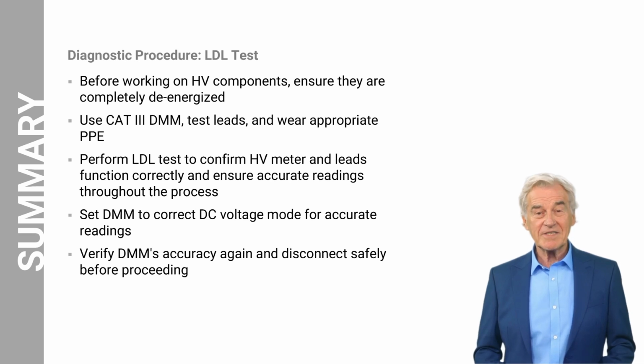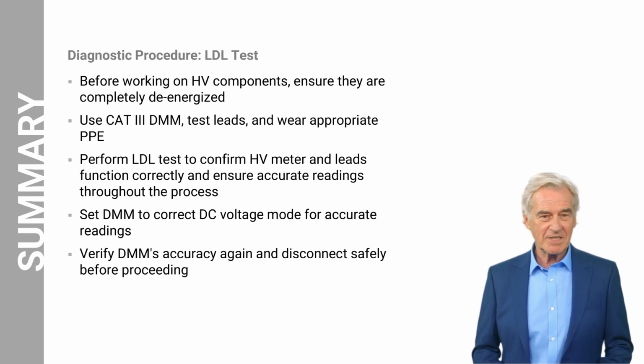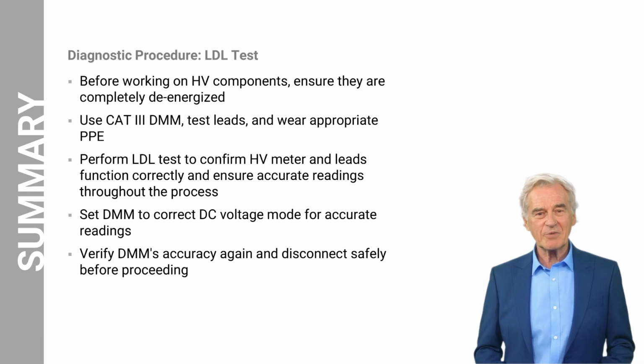Setting your multimeter to the correct DC voltage mode is critical for accurate readings, preventing false assumptions and potential safety hazards. Use the proper equipment and PPE, test HV circuits for low voltage, re-verify your meter's accuracy, and disconnect safely before proceeding further. Remember to always prioritize your safety and follow your manufacturer-specific instructions when working on HV systems.